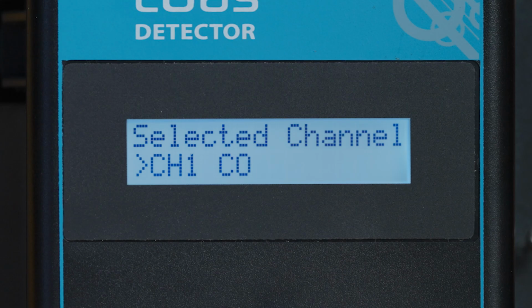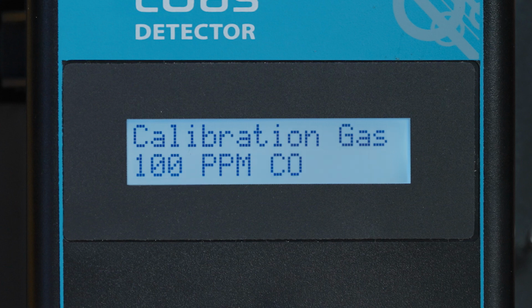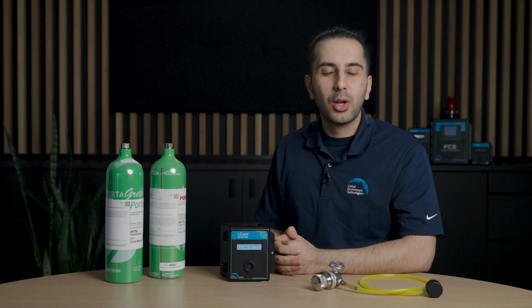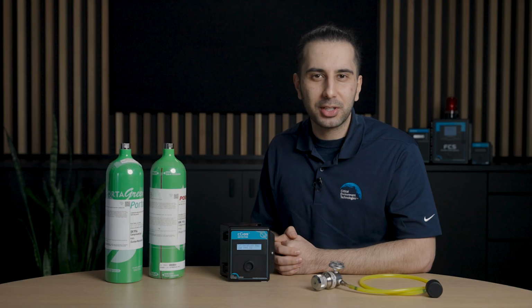We will select the first channel and navigate to calibration gas. Enter the gas concentration of the calibration span gas cylinder. In our case, it is 100 ppm carbon monoxide. Press OK to confirm. Next, we'll perform a zero calibration.